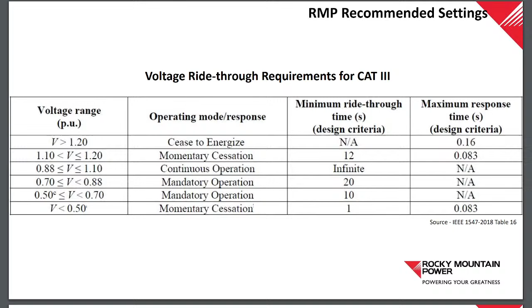This is the graph that is associated with that table we just went over. So these are the category 3 ride-through requirements, right? So that line up there in green, that dotted line, that's 1 per unit, which is 120 volts. So it goes up to 110% and down to 0.88 per unit. If the voltage is in that range, that inverter's not going to trip offline. It's going to continue, so you're going to get that ride-through. Whereas before, if you got some fluctuation, they would trip offline. And we're talking thousands of inverters. So every new inverter going forward is going to be set with category 3. So we feel good there.